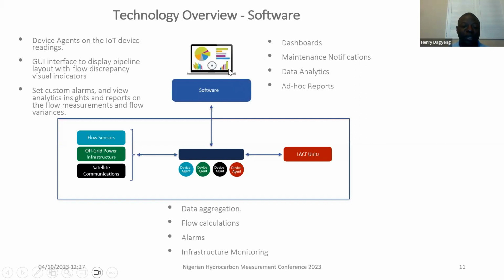An operator can have visuals, and we can set custom alarms. For example, if we're expecting a flow rate of maybe 10 meters per second, and this has reduced to maybe 6 or 7 meters per second, you get an alarm on the dashboard showing that something is happening at a specific location, since you have clamps all along the way. You can number them and identify in your software where an activity is going on.